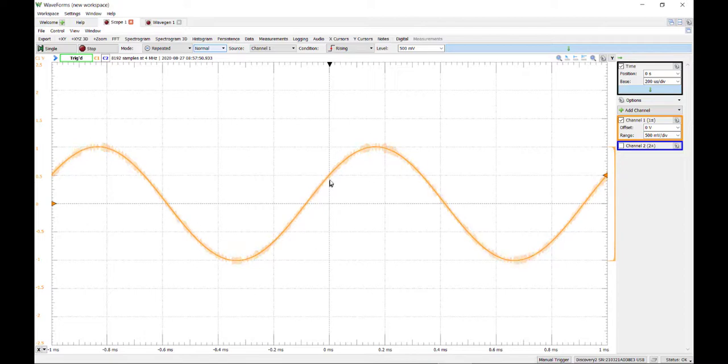And so I'm going to display that waveform, whatever I've got in the buffer, at that instant of time when it crosses that threshold. And because this is a buffer, I've got data back in time, I'm able to see, hey, what was coming beforehand? Because all that data is always going into a buffer, a first in, first out shift buffer, a circular buffer, and I can look back in time.